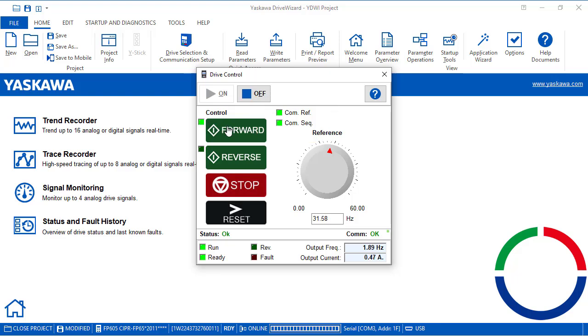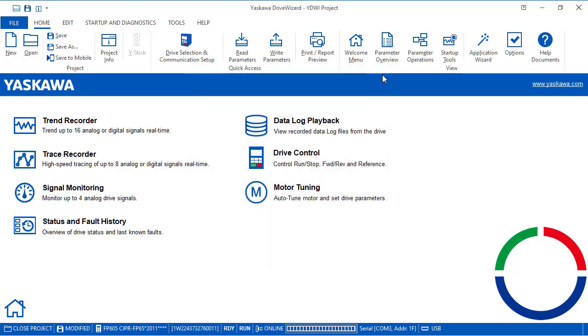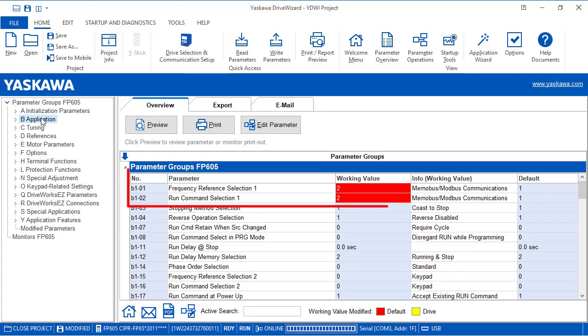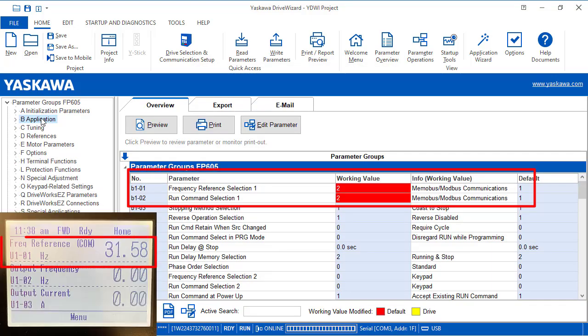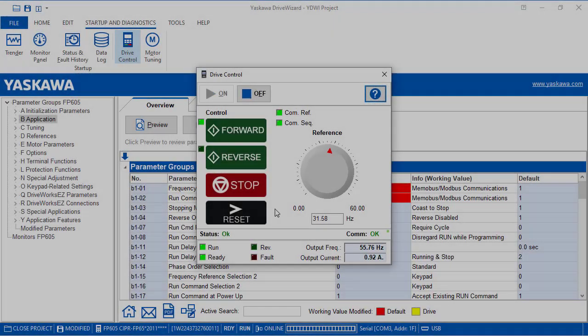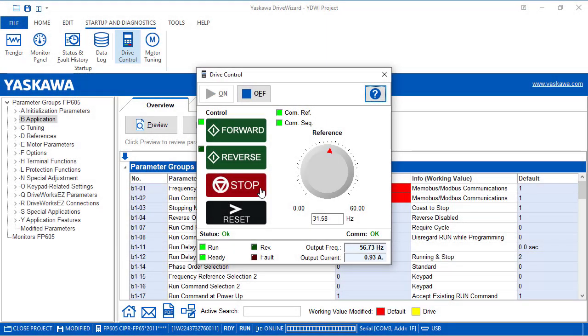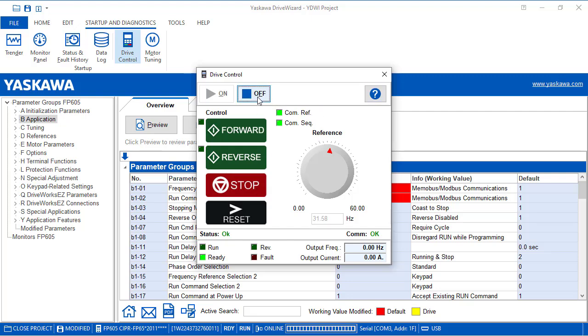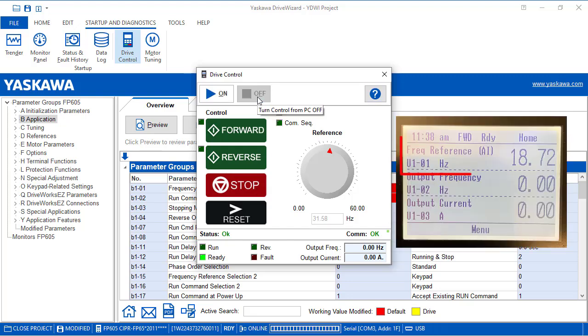If we had used the control and forgot to close it out correctly, then we can see that the drive's parameters are still set to comms. So make sure that you stop and click the off before disconnecting to return to normal operation.